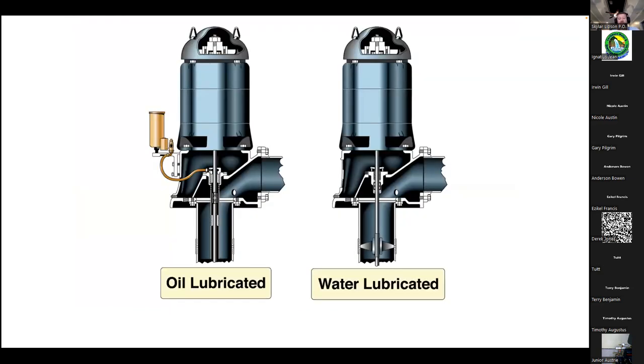Let's move over to sealing between the wet side and the dry side. Two different pumps shown here have packing — one is an oil-lubricated packing option. The area where the shaft runs through is called the stuffing box, and on top sits the packing gland. The water-lubricated style is more common in our industry and should have a constant drip of water from the top — this creates the seal, carries off heat, keeps out debris, and lubricates. Oil seal is also a plausible option.